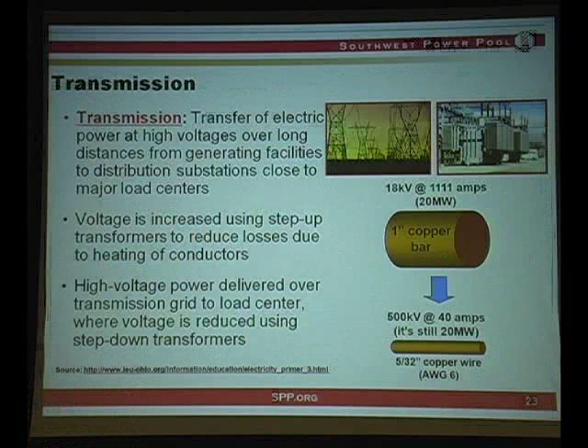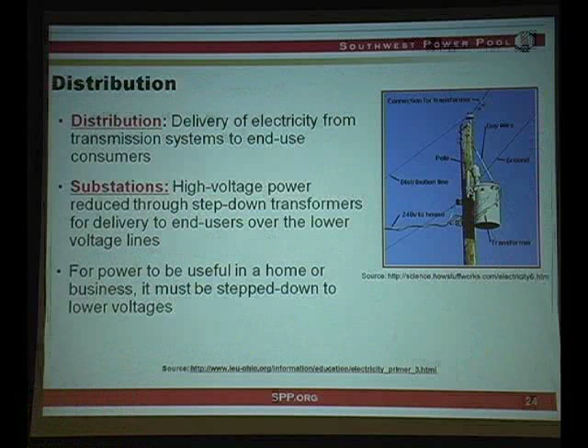When we talk about the distribution system, that's the lines and equipment you see in your neighborhoods - the lines typically running down your streets. You'll see pole-mounted transformers, which are very common, used to step down voltage to deliver to a house. You may also see big green boxes on the ground - those are pad mount transformers, used for underground electric service, where power runs into them and steps down as well.